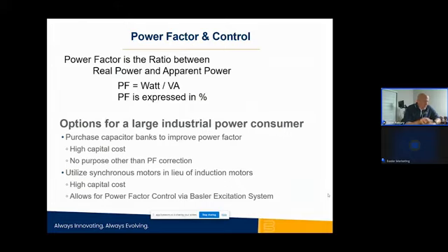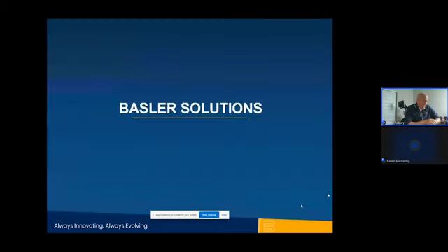So now we're going to talk about some of the Basler solutions. Basler's been involved in the synchronous motor business probably for 50 years. I know back in the day we used to use our DC power supplies. We called them the MVC, manual voltage control, and we would actually bias, or put in what we called an SCP-250, which was a VAR power factor controller.